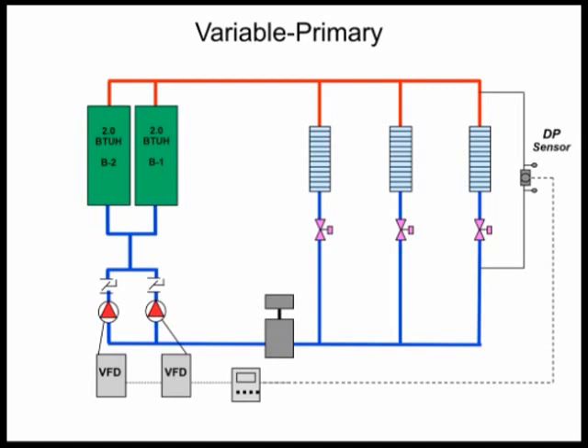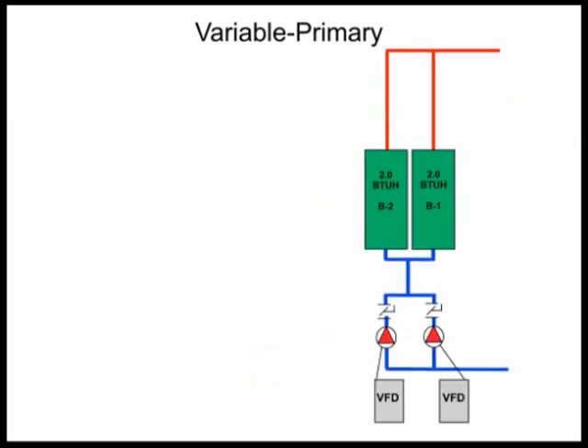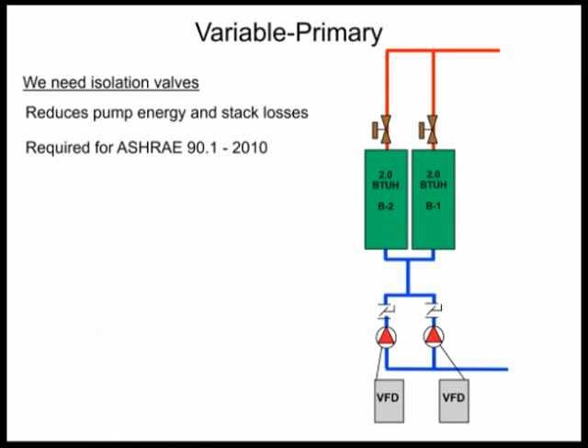There are only constant flow, constant speed pumps here. So we're going to pipe up this variable primary system. Do you see anything missing? One thing that's missing is isolation valves. These are a must. Isolation valves help reduce pump energy and stack losses, and they're also required for ASHRAE 90.1 2010.